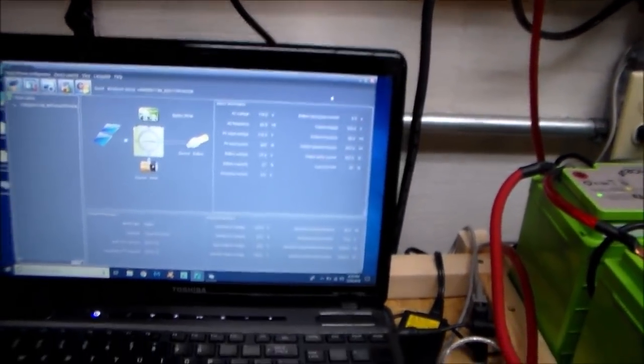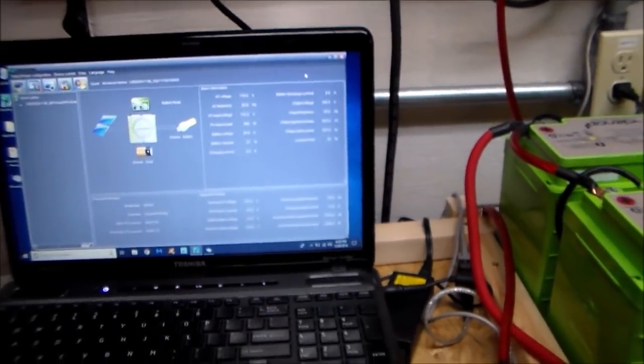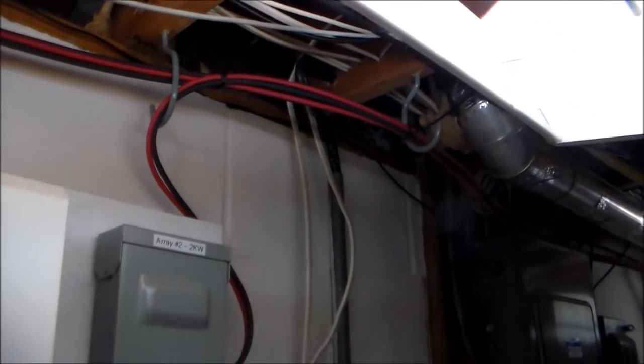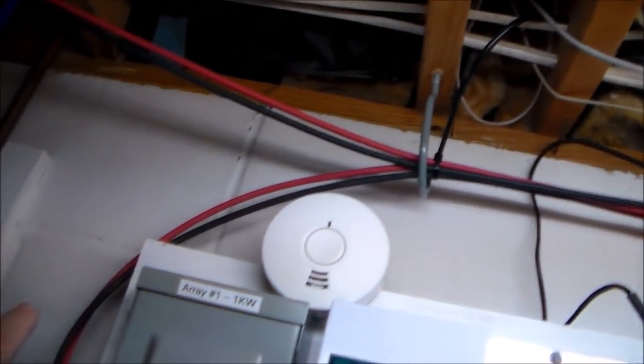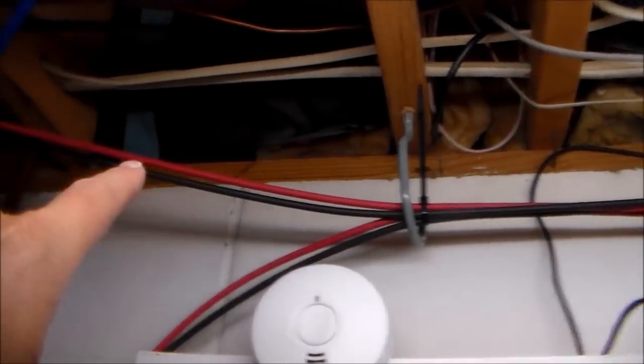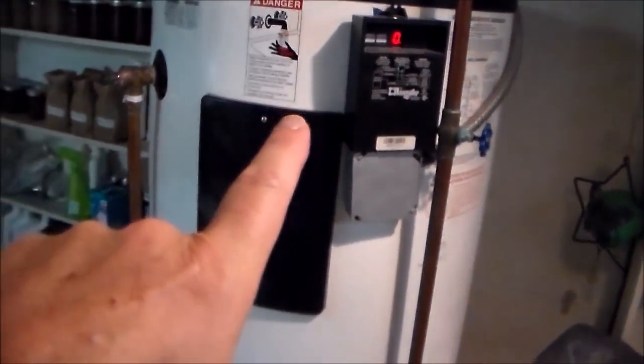The next thing I plan on doing is working a bit on the solar hot water system. I've got to finish up that rack. At the same time I ran my PV cables, the red and black ones, I've got one pair coming down to this quick disconnect, another over to this quick disconnect, and one more pair running across the ceiling that comes down behind my water heater. So next, when I get my panels mounted for the solar water heater, I'll be connecting into this, and doing a quick modification to this 85-gallon hot water heater.